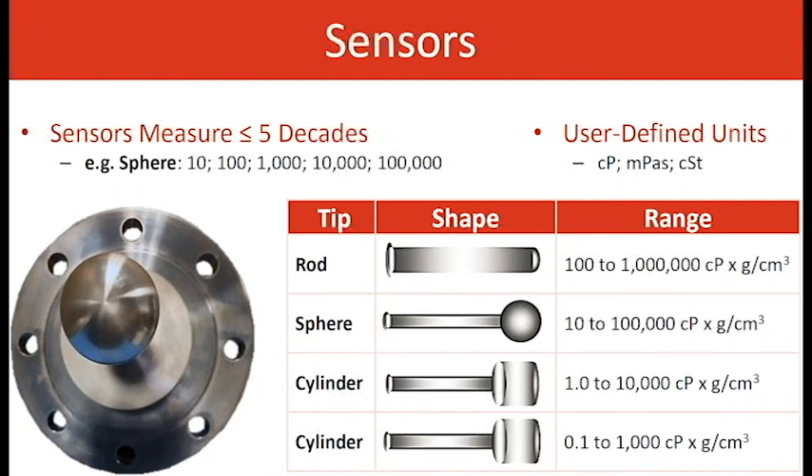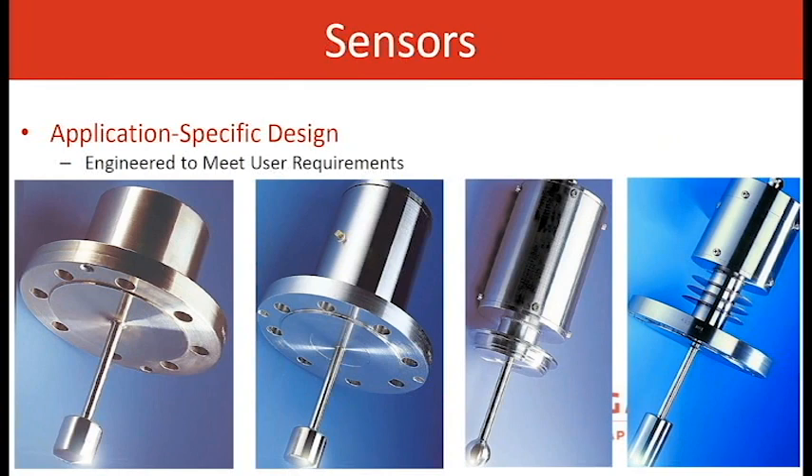The user-defined limits involve the viscosity calculation, and units include centipoise and millipascal seconds. The two pictures on the left show different flange sizes and different models, but the tip is the same — the 1.5 by 1.5 cylinder, up to 10,000 centipoise. The third picture is a sphere sensor — up to 100,000 centipoise — with a sanitary flange mounting. The sensor on the right is the larger cylinder, with fins for cooling, and that is the 1,000 centipoise max design.